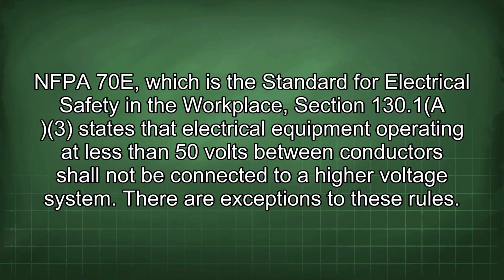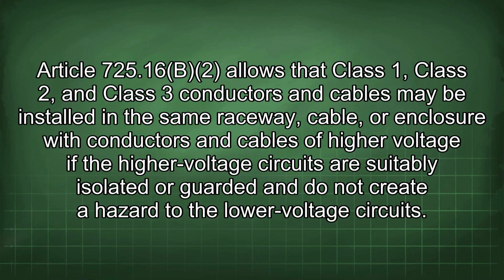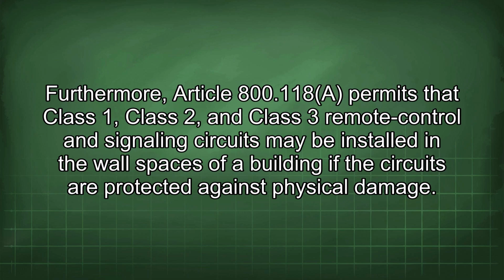There are exceptions to these rules. Article 725.16(B)(2) allows that Class 1, Class 2, and Class 3 conductors and cables may be installed in the same raceway, cable, or enclosure with conductors and cables of higher voltage if the higher voltage circuits are suitably isolated or guarded and do not create a hazard to the low voltage circuits. Furthermore, Article 800.118 permits that Class 1, Class 2, and Class 3 remote control and signaling circuits may be installed in the wall spaces of a building if the circuits are protected against physical damage.